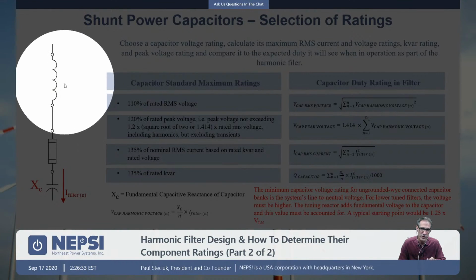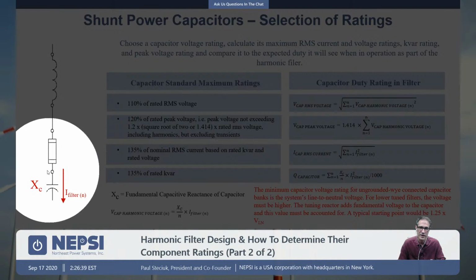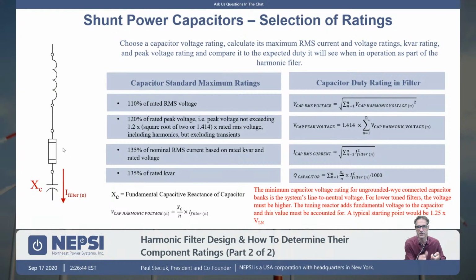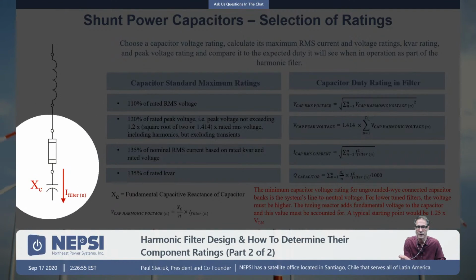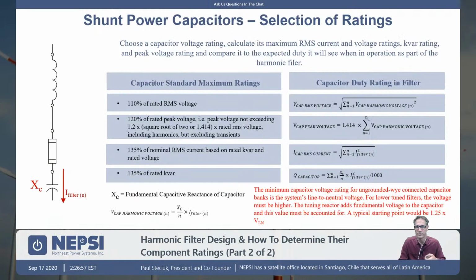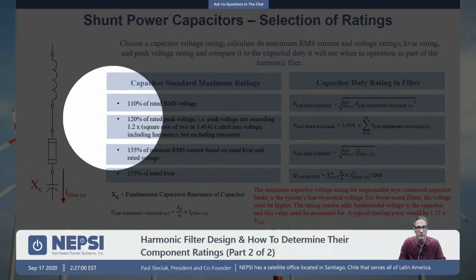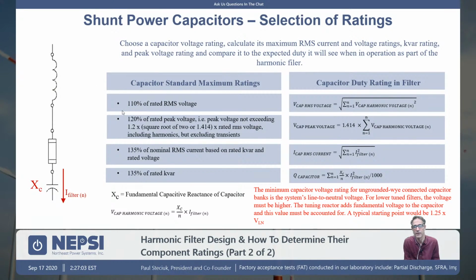So when you put a capacitor in a filter, you get a voltage rise across the reactor, and that's counterintuitive. This capacitor will actually have a higher fundamental voltage than the line to neutral voltage here. Okay, so we have a higher voltage from the fundamental. We would have to account for that, and then you have to add to that all your harmonic voltages. Okay, so IF at the harmonic times XC at the harmonic impedance, come up with the value of voltage, and from there we can calculate an RMS voltage.